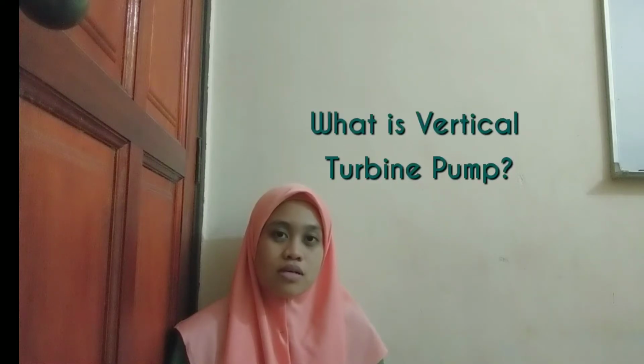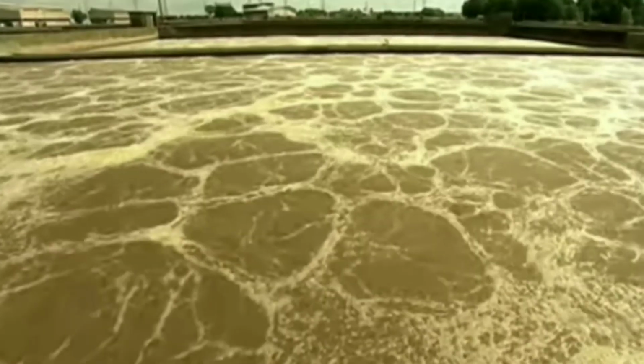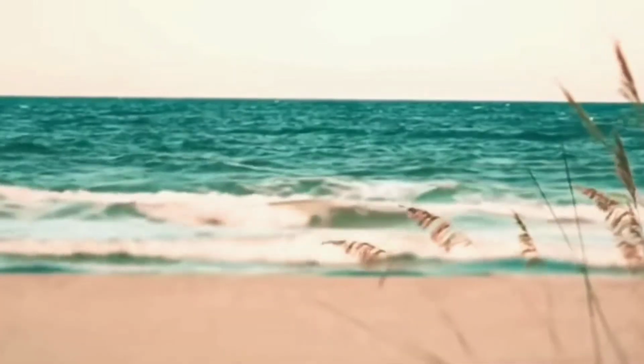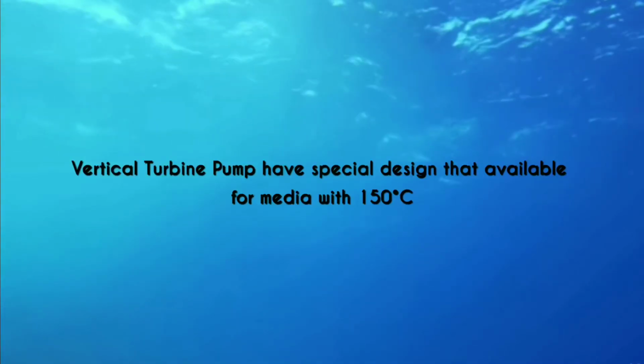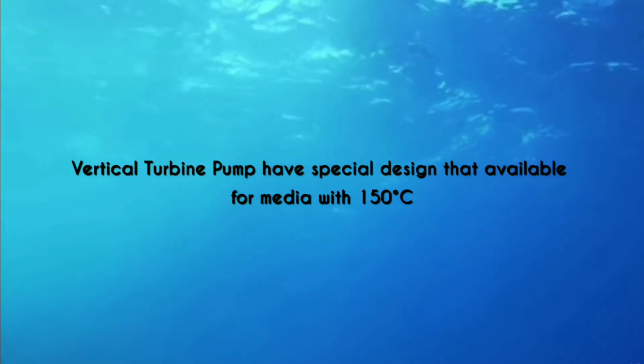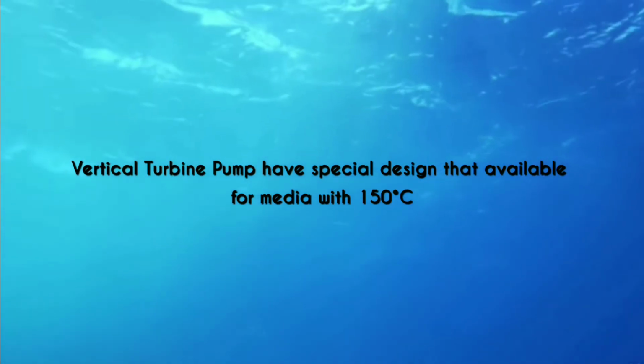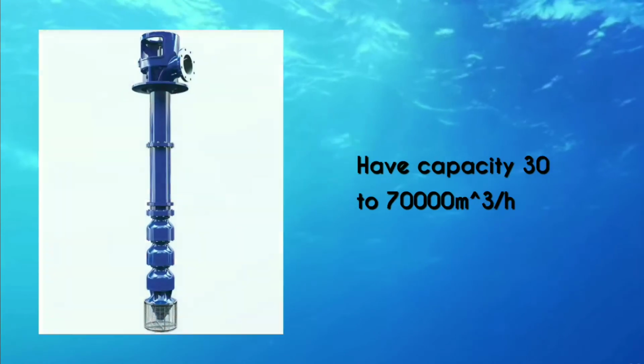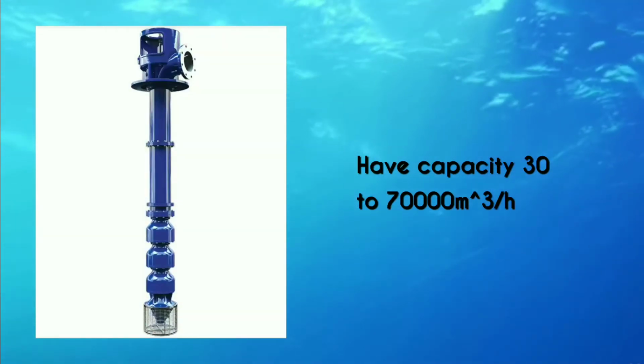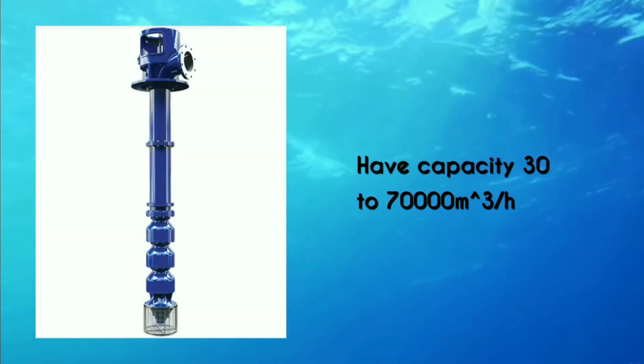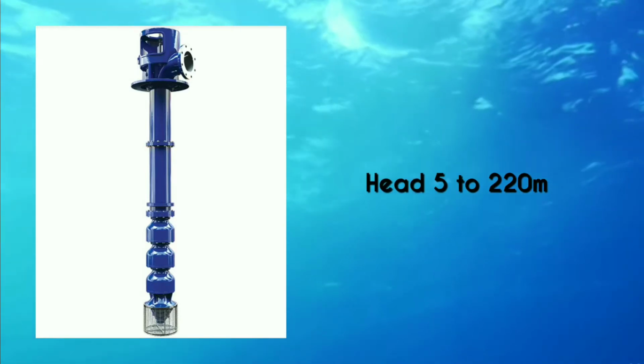A vertical turbine pump is a centrifugal pump specially designed to move water from a well underground or a reservoir. It is designed to move clear water, rainwater, water in an iron sheet pit, sewage, and seawater under 55 Celsius, but it also has a special design available for media up to 150 Celsius. It has a capacity of 30 to 70,000 cubic meters per hour and a head of 5 to 220 meters.